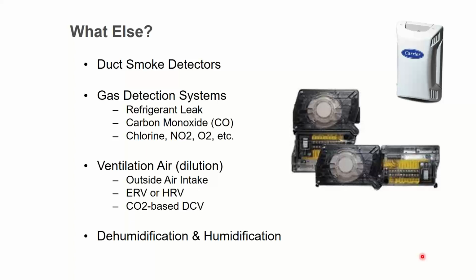One of those requires it on the supply, one on the return. I don't remember which is which. If you're in a town that's following both IMC and NFPA, you'd have to put a detector on both the supply and the return. And then both of those codes, IMC and NFPA, at 15,000 CFM, always require a detector on both the supply and the return.